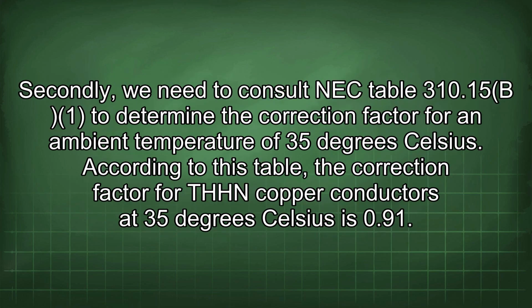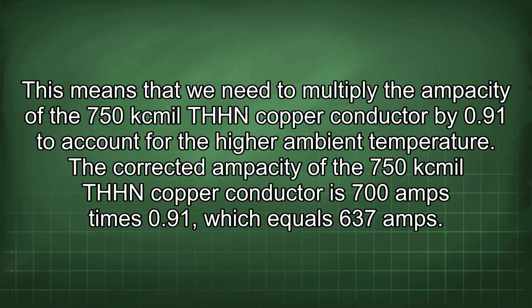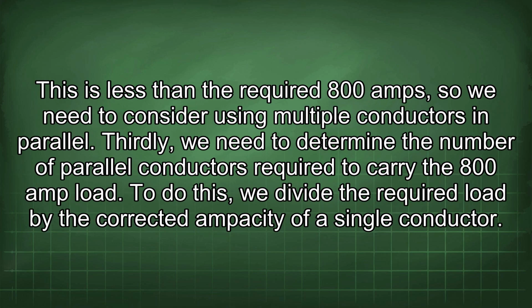Secondly, we need to consult NEC Table 310.15(B)(2)(a) to determine the correction factor for an ambient temperature of 35 degrees Celsius. According to this table, the correction factor for THHN copper conductors at 35 degrees Celsius is 0.91. This means that we need to multiply the ampacity of the 750 kcmil THHN copper conductor by 0.91 to account for the higher ambient temperature. The corrected ampacity of the 750 kcmil THHN copper conductor is 700 amps times 0.91, which equals 637 amps. This is less than the required 800 amps, so we need to consider using multiple conductors in parallel.